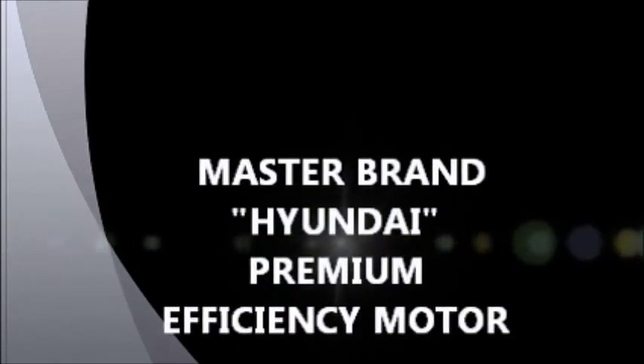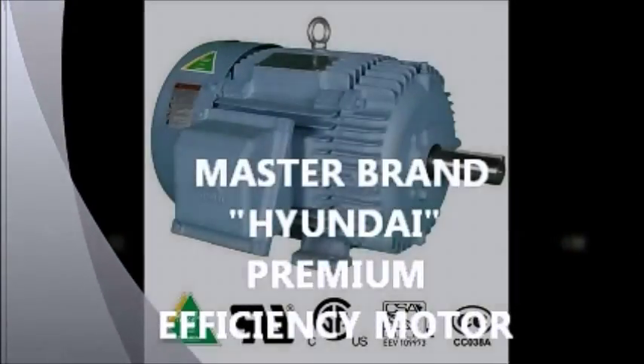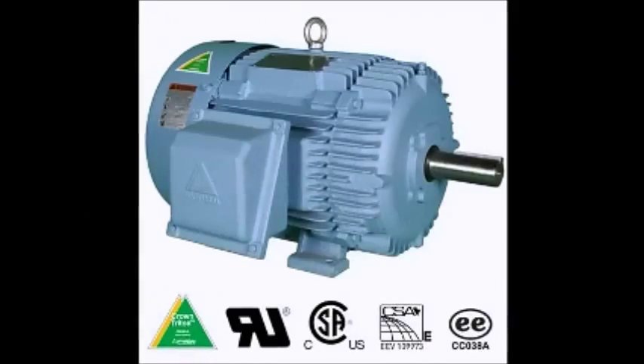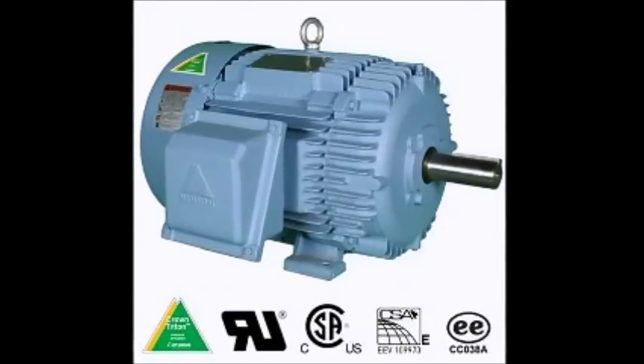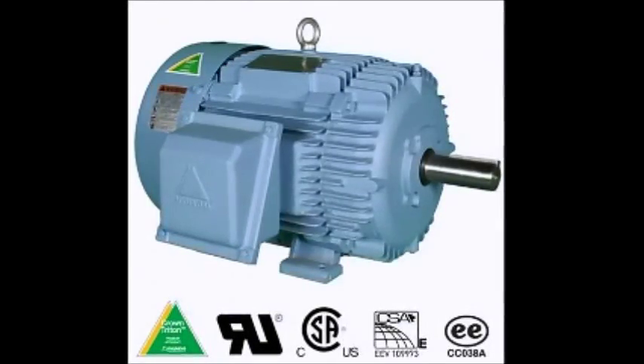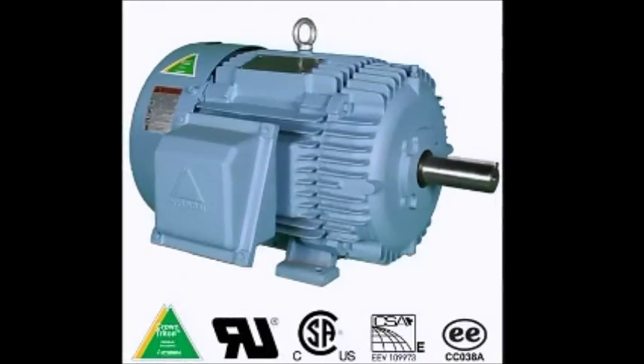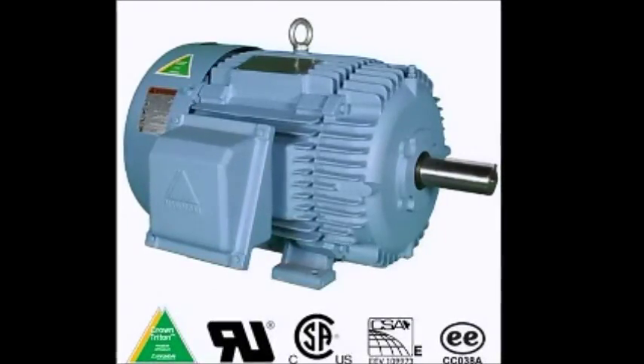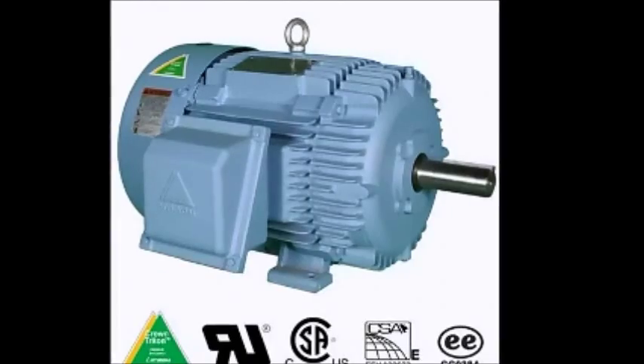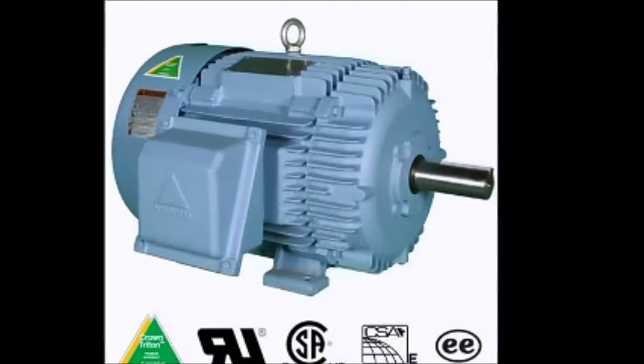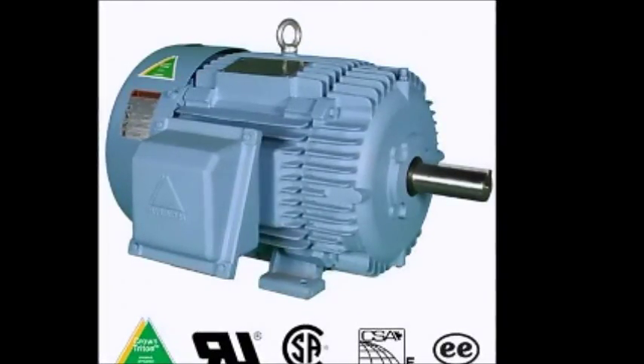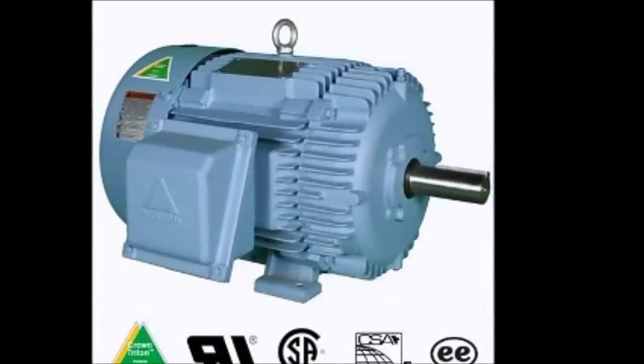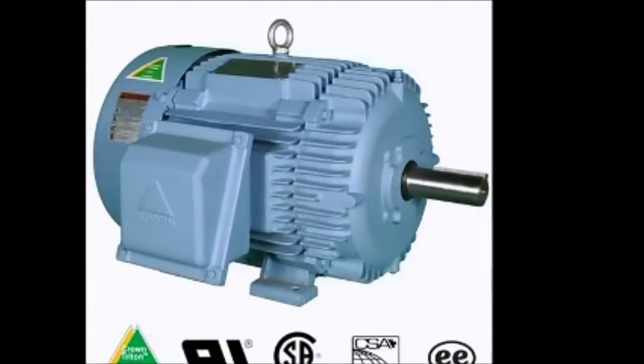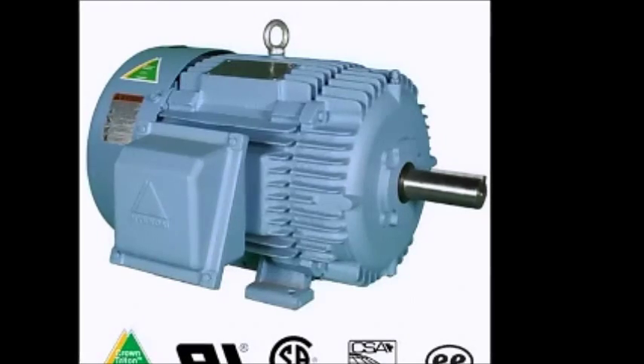The Hyundai Motor supplies the muscle for the rotary screw compressor. The motor operates at 1750 RPMs with 4-pole starting torque and low harmonic distortion, which reduces motor noise. Here are some additional features of the motor. Premium motor bearings produce a 60,000 hour motor life. Flexible voltage range of 208, 230, 380, 460, and special order 575.